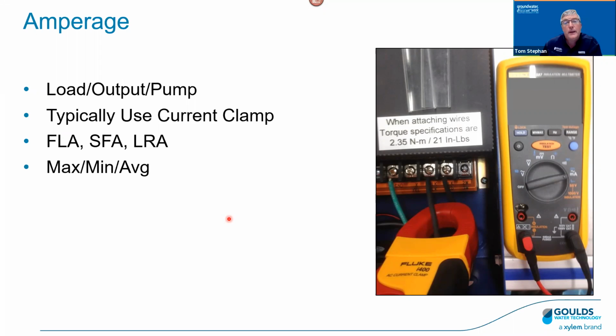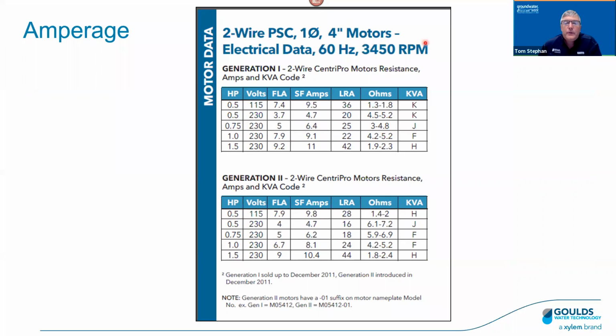Now, for the pumps we're talking about today, the smaller, lower horsepower submersibles, we do know that they often run in service factor. So we need to be looking at the service factor amps as opposed to the full load amps in determining if it's high or not, right? Okay, here's amperage. You can look at the control box, let's say it's a 3-wire, which has some information on there. We should probably be a little bit cautious about that because maybe that control box was added later and doesn't quite match up to the original motor that was installed. So it's always good to look that up. Let's take a quick look here at your 2-wire single phase motors and pick on the half, 230 again. We can see 4.7 service factor amps.